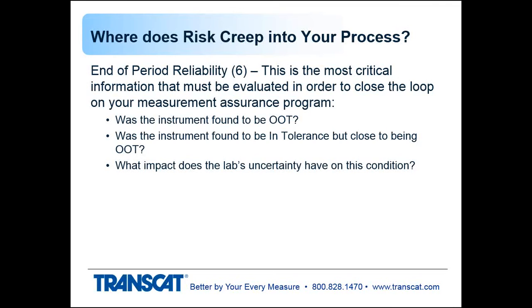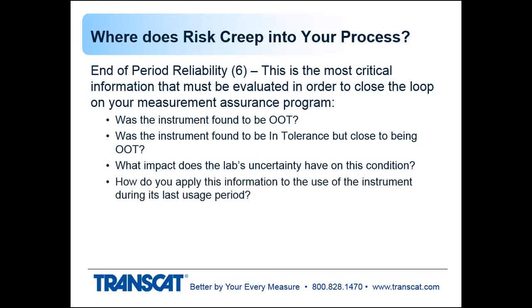There are other webinars that get into more details with that information if you're interested. But that's something to consider. How good is the lab's measurement in determining the instrument's value? And how do you apply all that information to use the instrument during its last usage period? How do you take those readings, whether close to being out of tolerance or absolutely out of tolerance, and apply that back to the places where the instrument was used over its last cal interval to determine whether those offsets in the instrument had any impact on the decisions that were made?